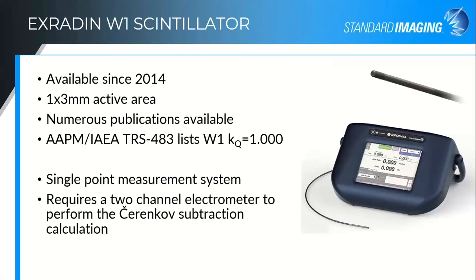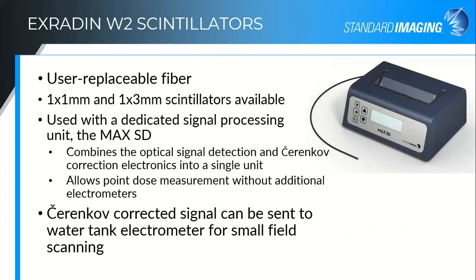I would caution you to be aware of the low signal limitations of your electrometer. It does require very high sensitivity and high accuracy for the low currents you're getting from the light from the scintillator.